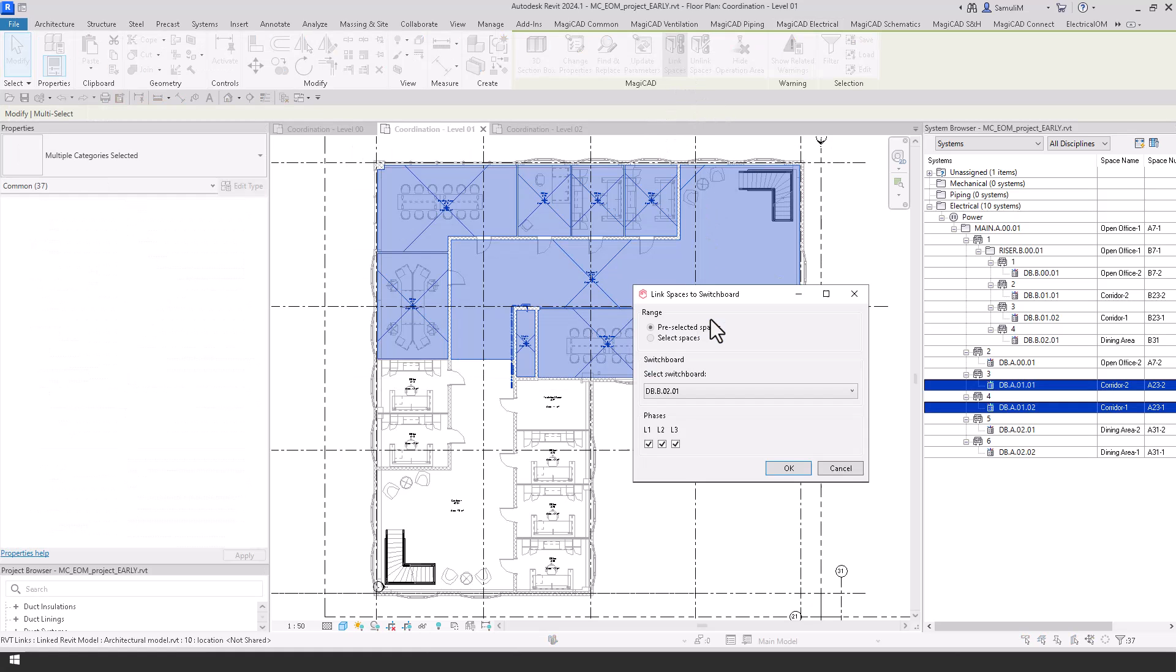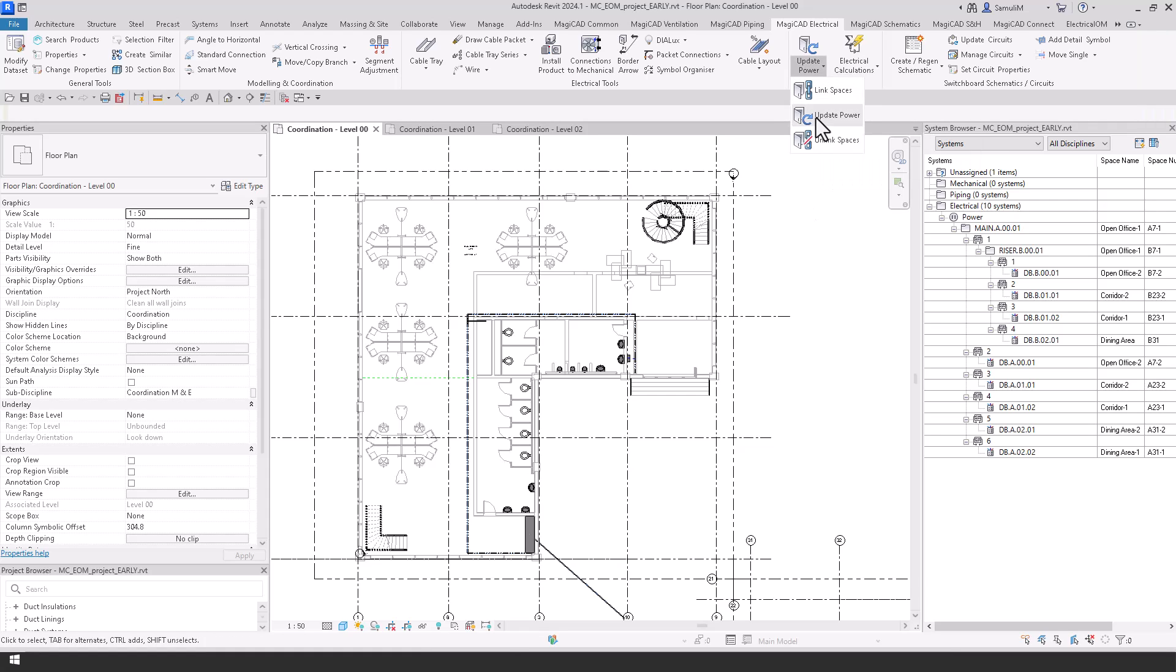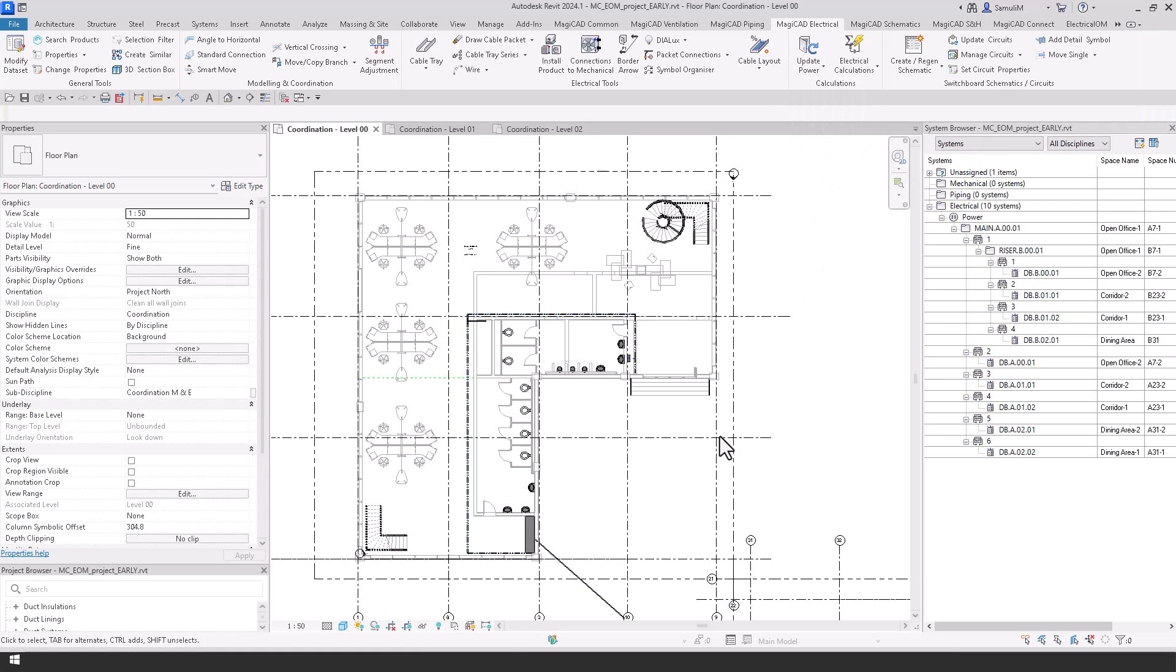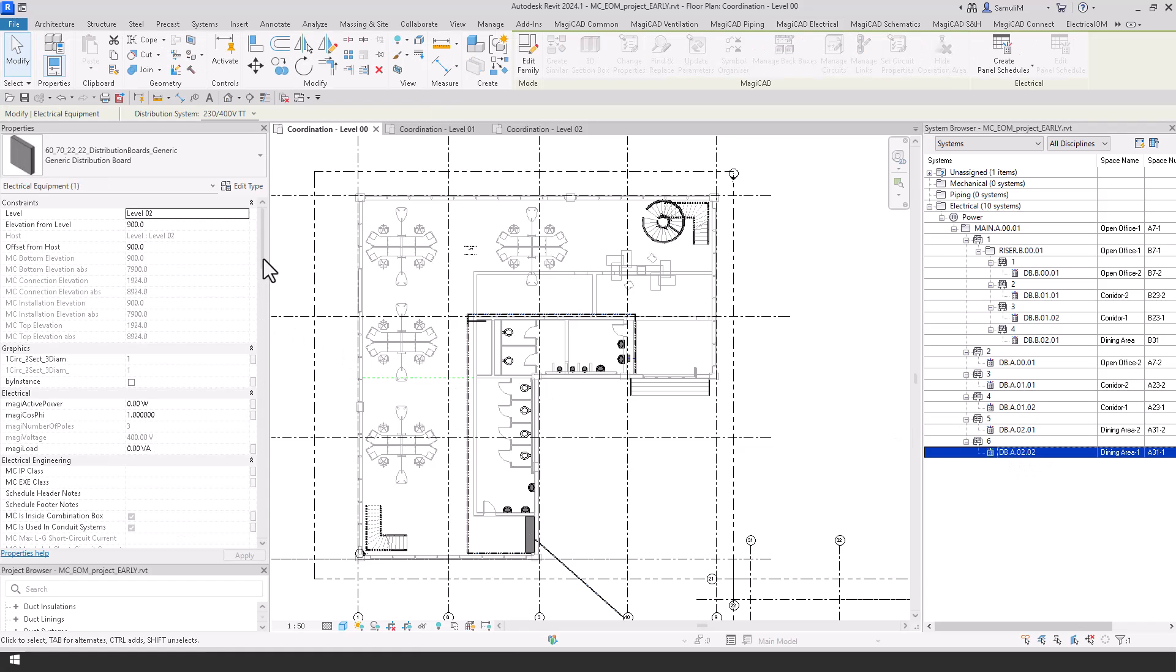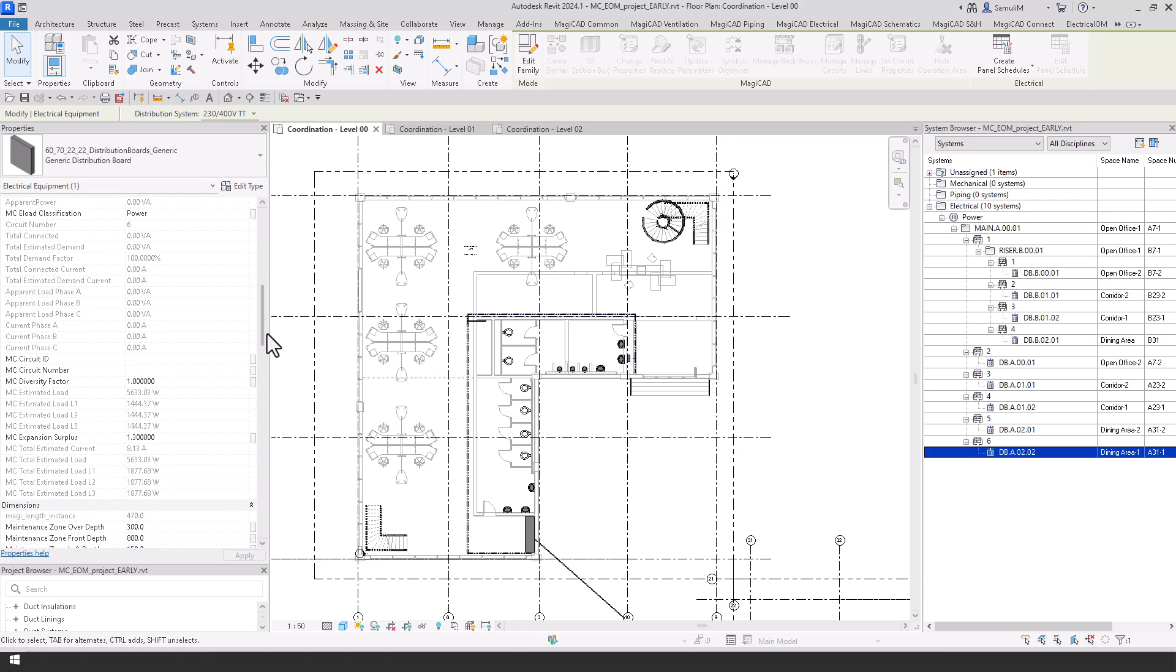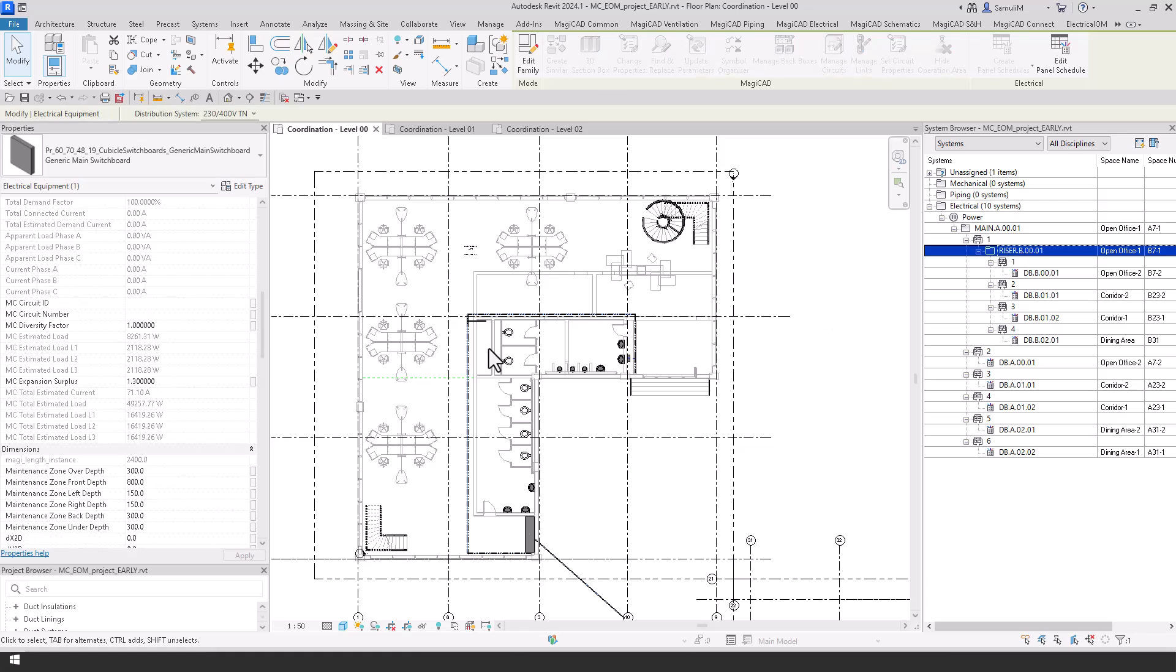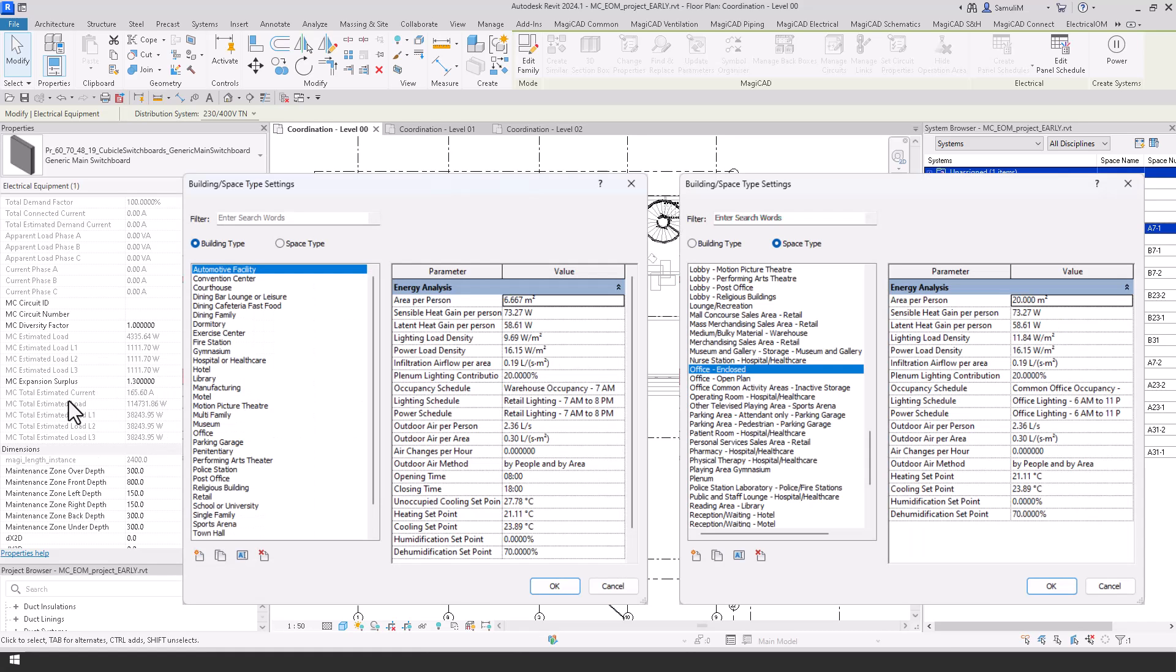And what's happening here is the loads are being pushed into the boards that have been selected in the model. And these spaces, all the loads within the spaces are being added to the boards. And now once we've done this what we can do is we can jump on here and update the power in these spaces. And if you select the system you can see here that for each phase within that board has been shown in the properties.